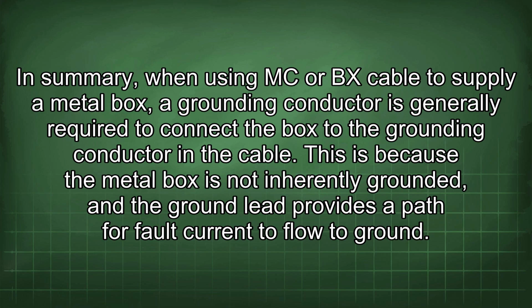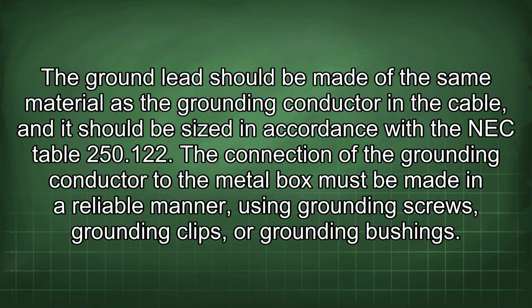In summary, when using MC or BX cable to supply a metal box, a grounding conductor is generally required to connect the box to the grounding conductor in the cable. This is because the metal box is not inherently grounded, and the ground lead provides a path for fault current to flow to ground. The ground lead should be made of the same material as the grounding conductor in the cable, and it should be sized in accordance with NEC Table 250.122. The connection of the grounding conductor to the metal box must be made in a reliable manner, using grounding screws, grounding clips, or grounding bushings.